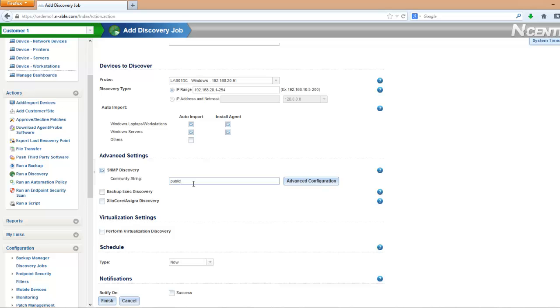Now, using SNMP here, I also want this installed and configured on some of my Windows servers. If I have Dell hardware, for example, or maybe HP hardware, if you install Dell Open Manage, or leave it installed from the vendor, and install and enable SNMP, when we scan that device with a discovery job, we'll actually discover the hardware from the vendor and automatically apply hardware monitoring. So RAID status, temperature, fan status, etc. So SNMP is going to be important on network gear, and on physical servers.